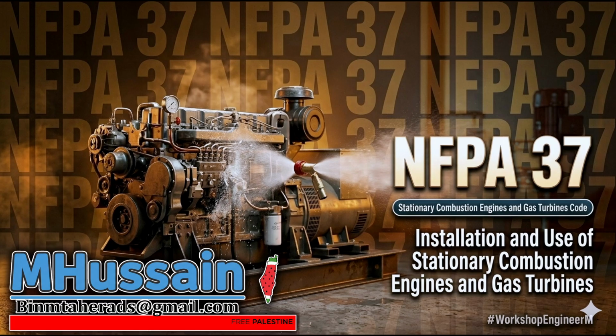They couldn't move the heat source, so they changed the properties of the wall. They built a 1-hour fire-rated masonry brick barrier in that 3-foot gap between the generator and the building. A thermal shield. The radiant heat from a fire would strike the brick, not the wood siding. It neutralizes the proximity hazard. Basically, they built a fire-rated moat.